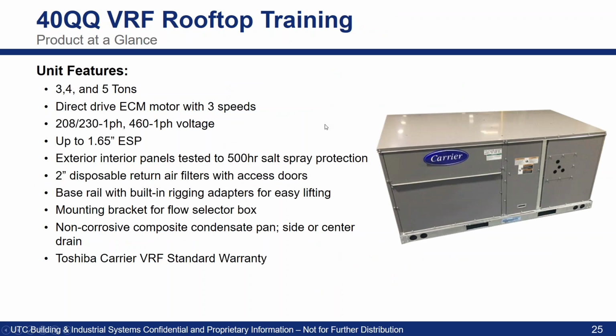These come up, they're a rarity, but Carrier does have a fan coil, or it is actually a rooftop unit that will fit on our legacy footprints. So if for whatever reason you have an owner that wants to go VRF, we can't do the traditional route where we're mounting VRF fan coils indoors, and they have some existing Carrier rooftop units, we do have an option for you there. We really have to look at the application and what the needs are. Just because of our heating demands here in Chicago, we got to remember that this is a heat pump, right? So we just need to be careful there.